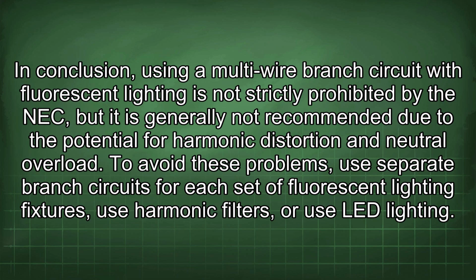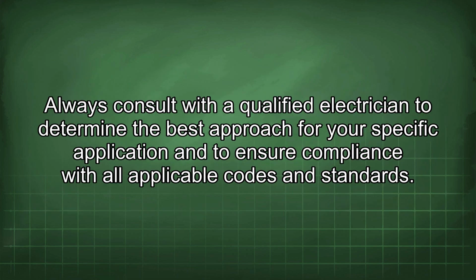In conclusion, using a multi-wire branch circuit with fluorescent lighting is not strictly prohibited by the NEC, but it is generally not recommended due to the potential for harmonic distortion and neutral overload. To avoid these problems, use separate branch circuits for each set of fluorescent lighting fixtures, use harmonic filters, or use LED lighting. Always consult with a qualified electrician to determine the best approach for your specific application and to ensure compliance with all applicable codes and standards.